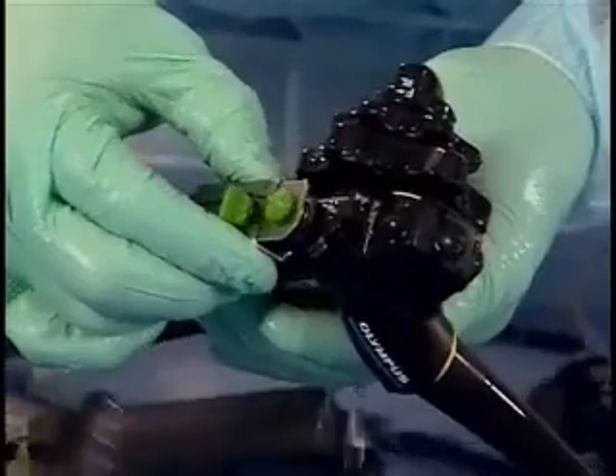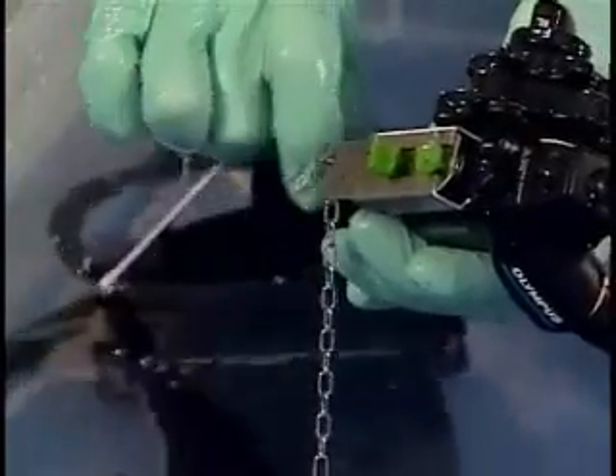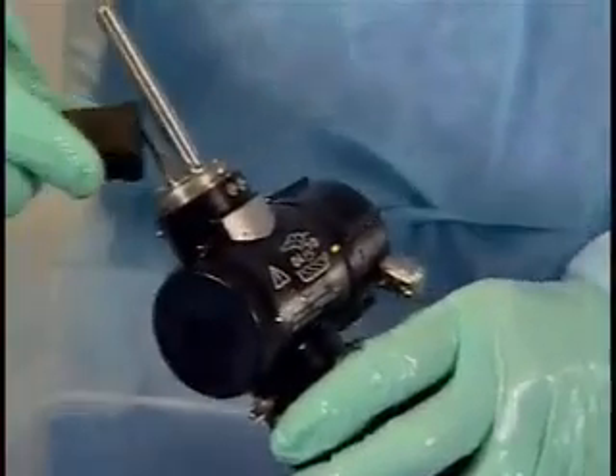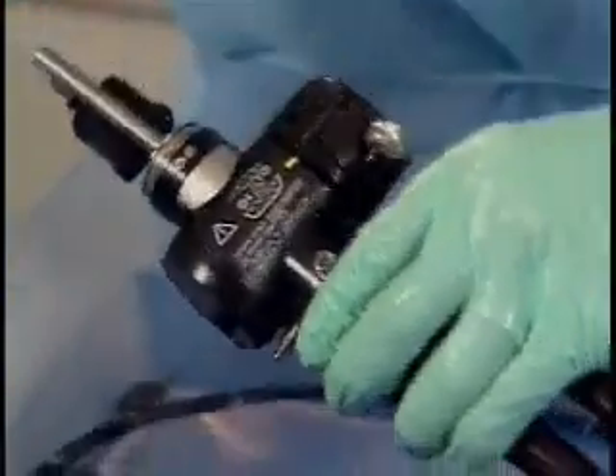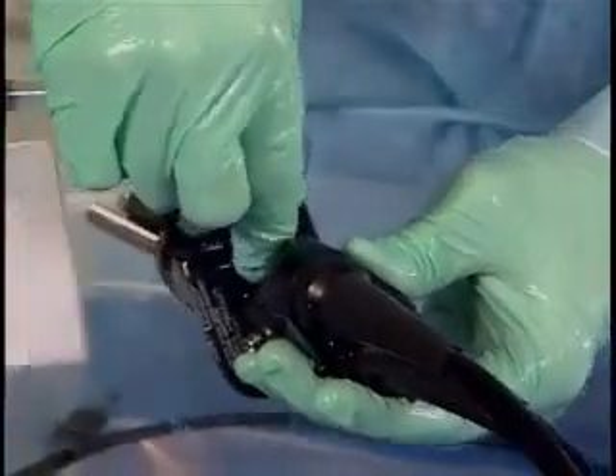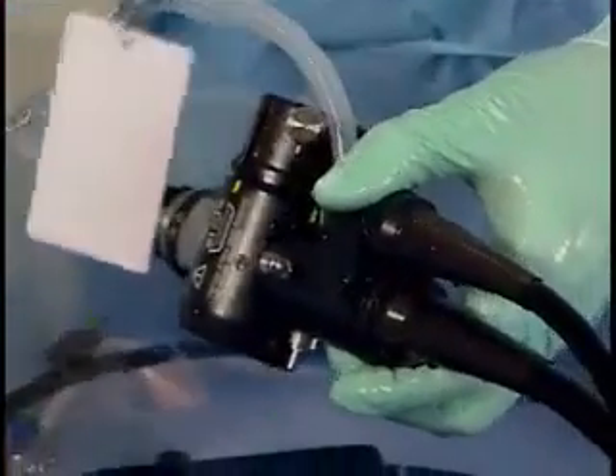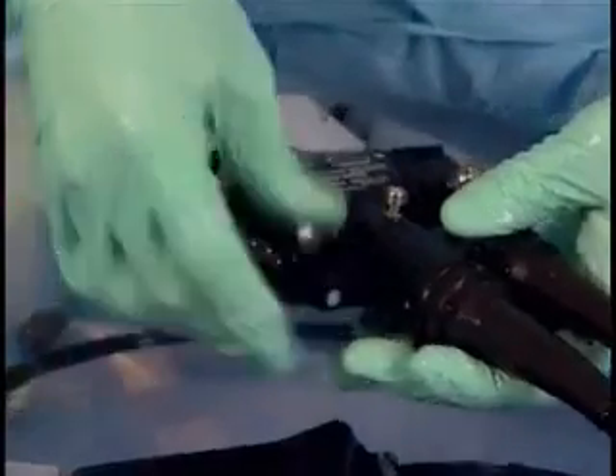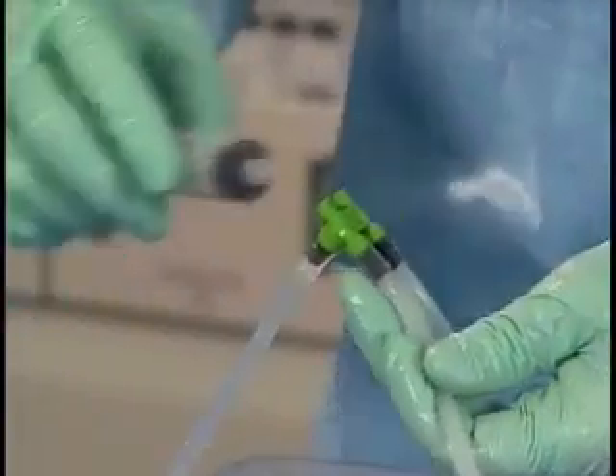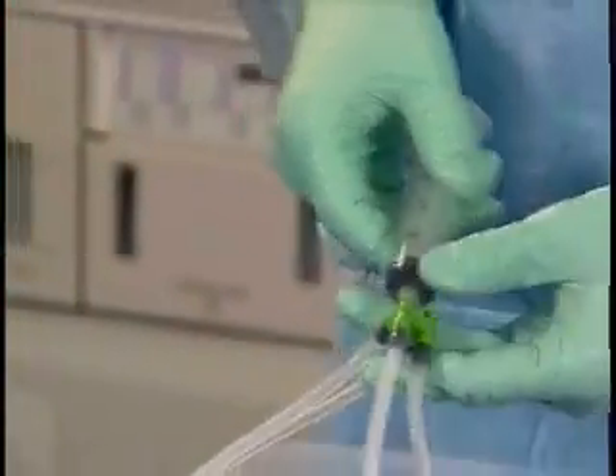To flush the air-water channel, attach the channel plug to the valve cylinders and the instrument channel adapter to the instrument port if you are reprocessing a CLA scope. Attach the injection tube to the air pipe, the suction port, and the water and air connectors. Next, attach a 30 cc syringe to the air-water channel port of the injection tube.